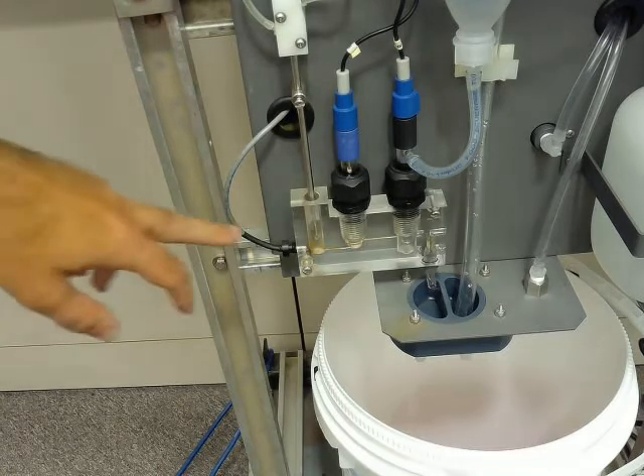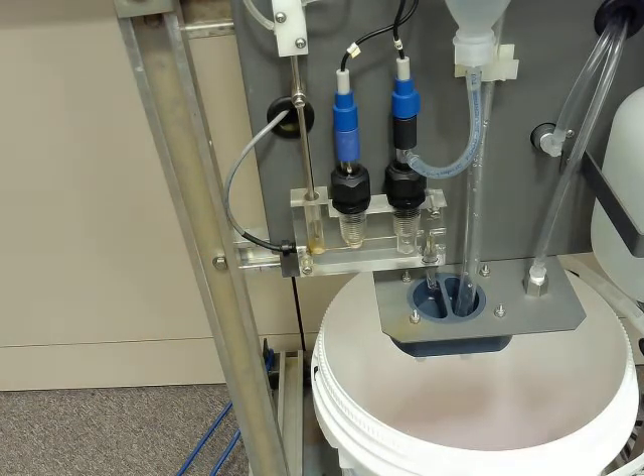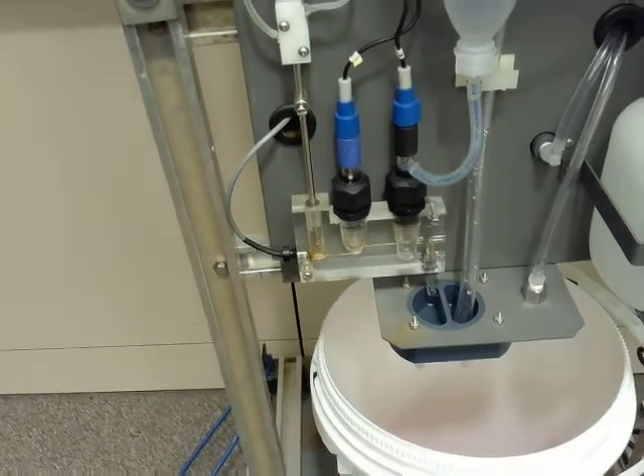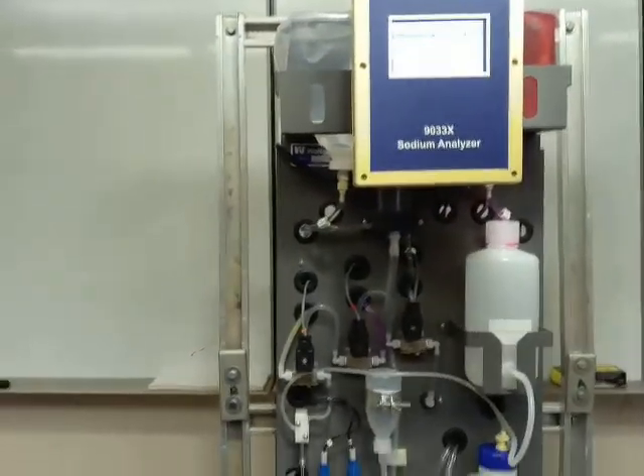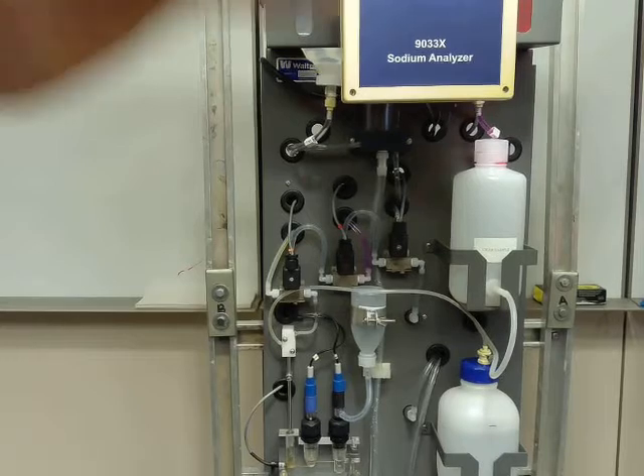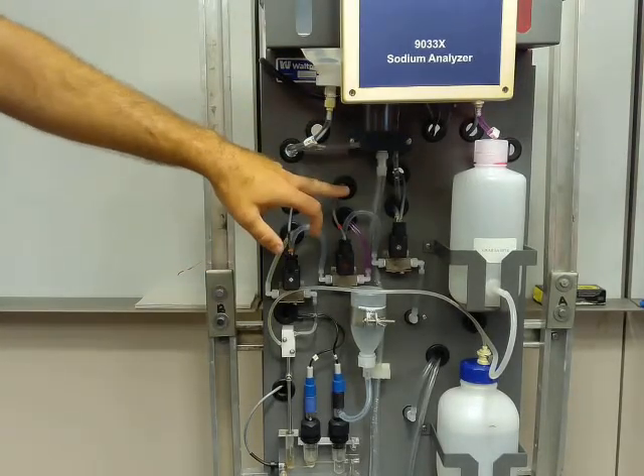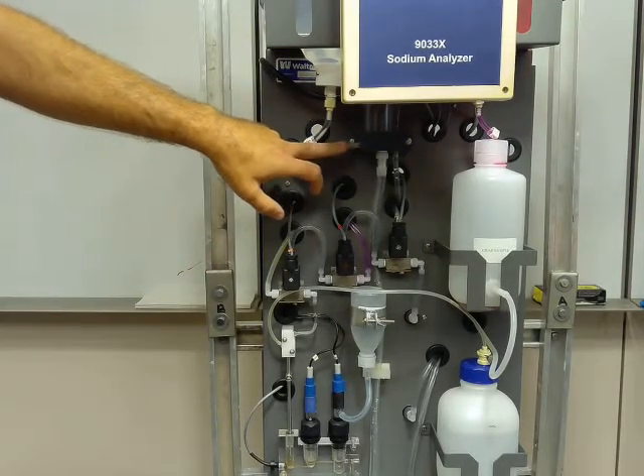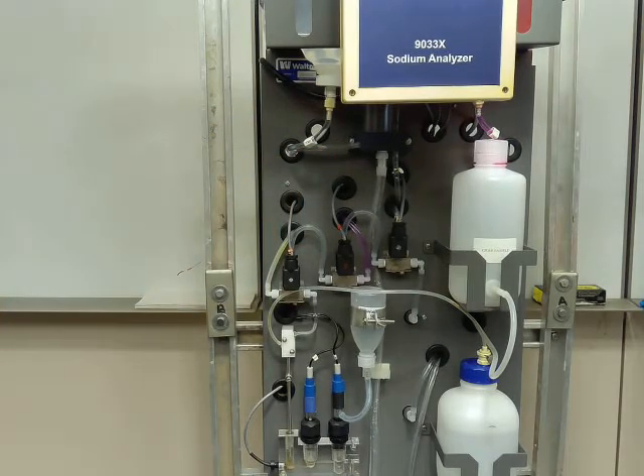But back to this bubbling, this flow is a big part of the operation of the analyzer. And one thing you notice if we go back and look at the whole system architecture, we touched on the constant head block up here. Once our sample comes past this constant head block, all the flow is basically just gravity fed. So it's going to flow through. There's really no back pressure behind the system. And what that does is it helps for a very constant flow, hence the term constant head.